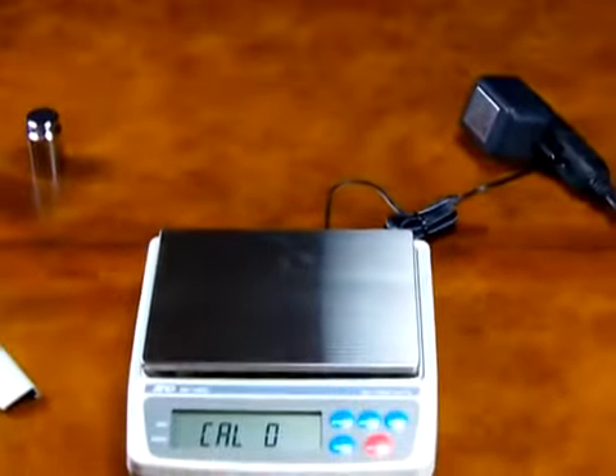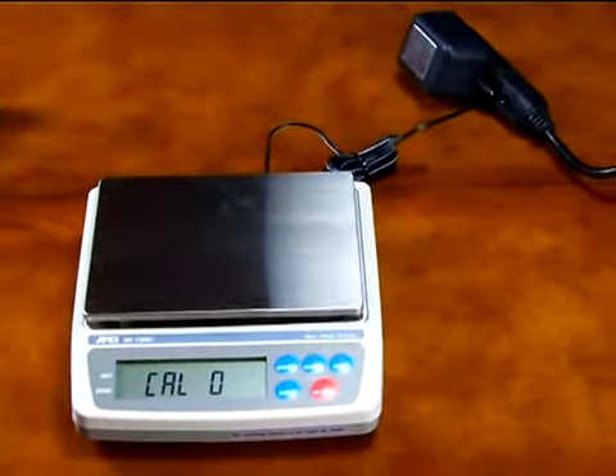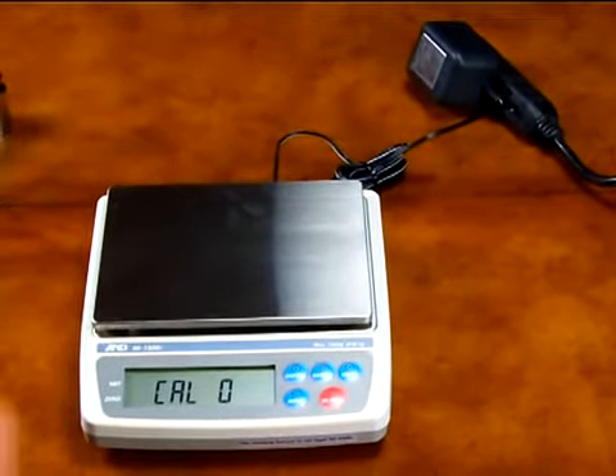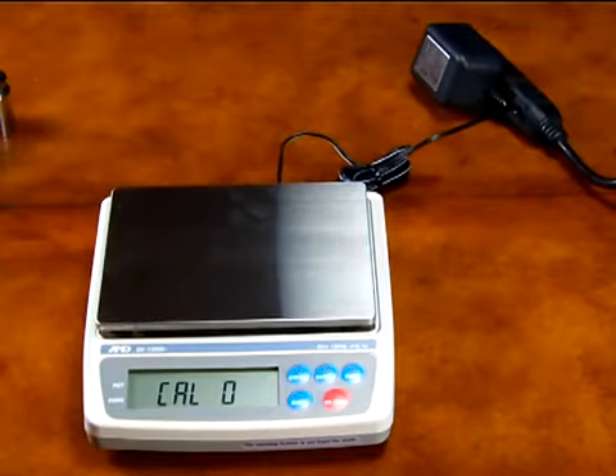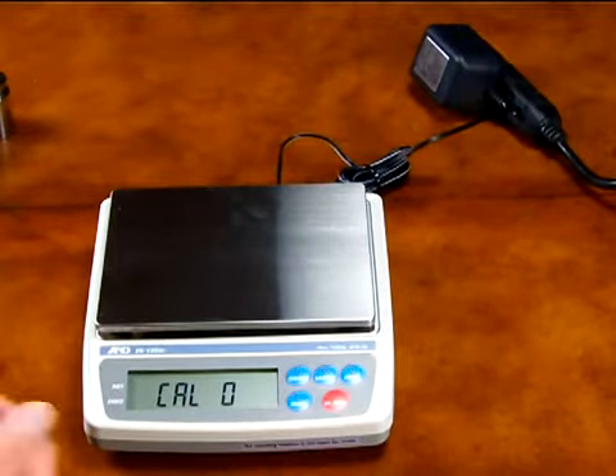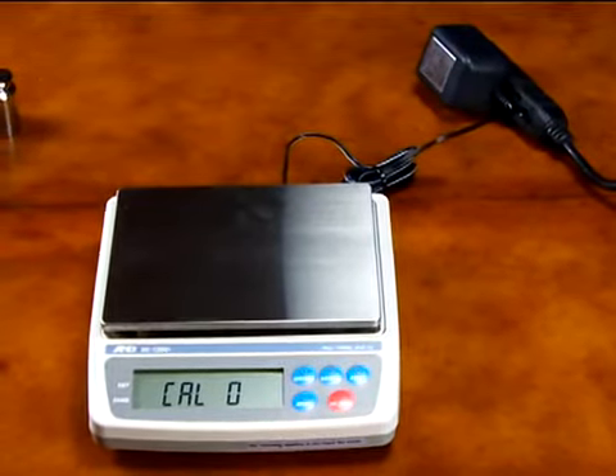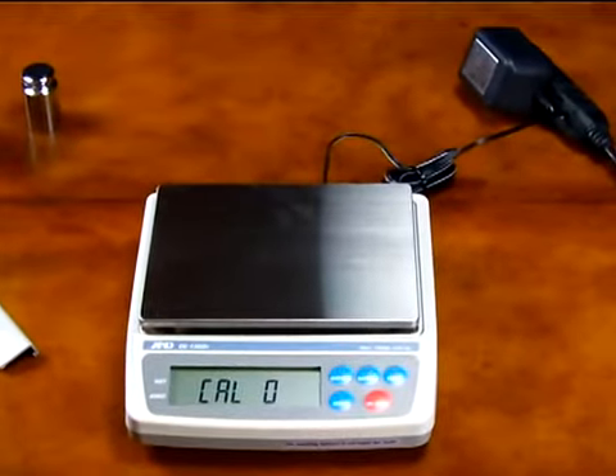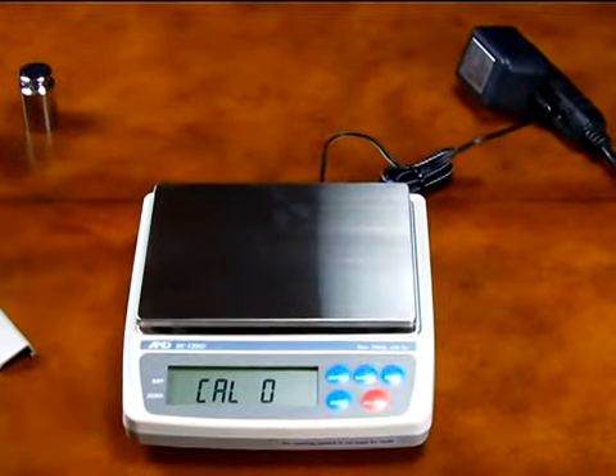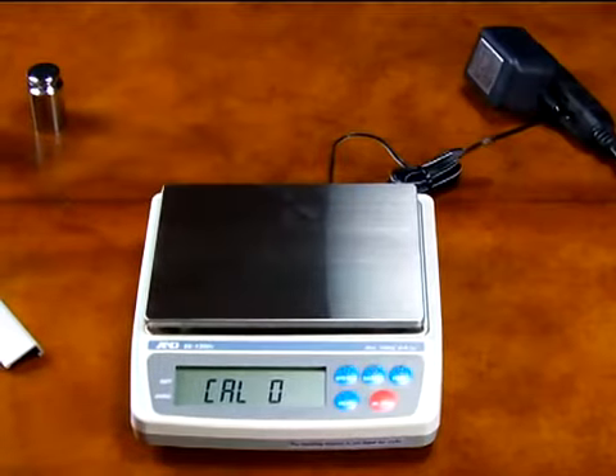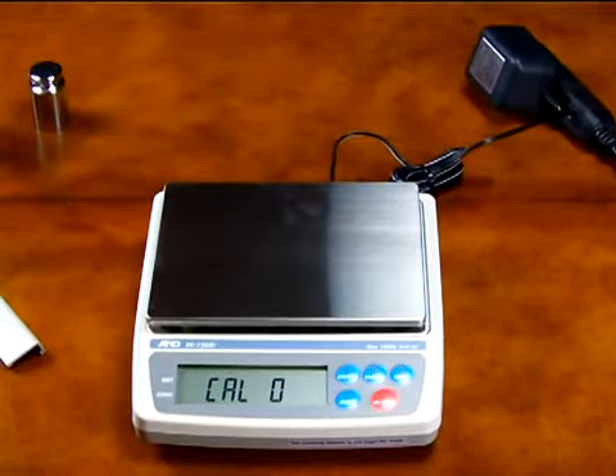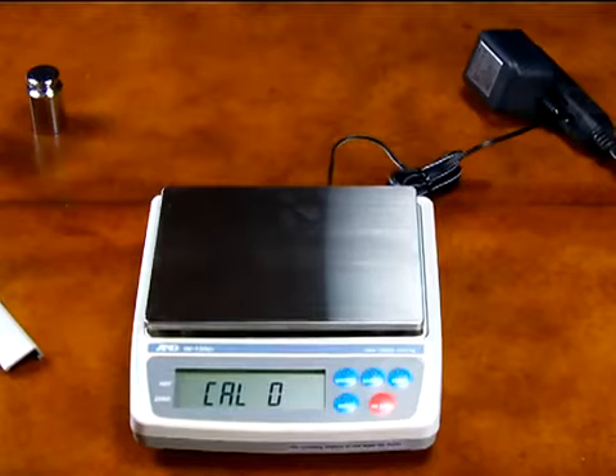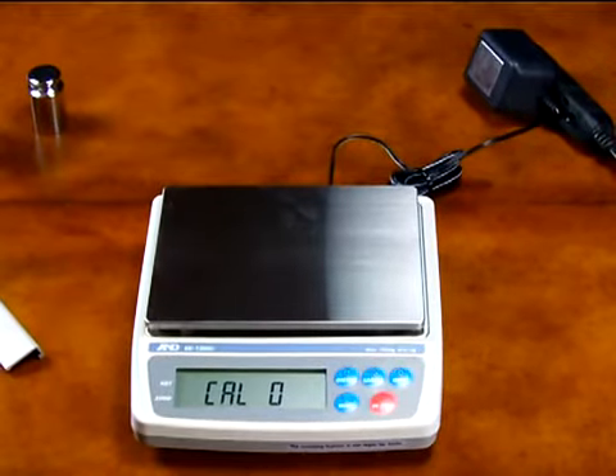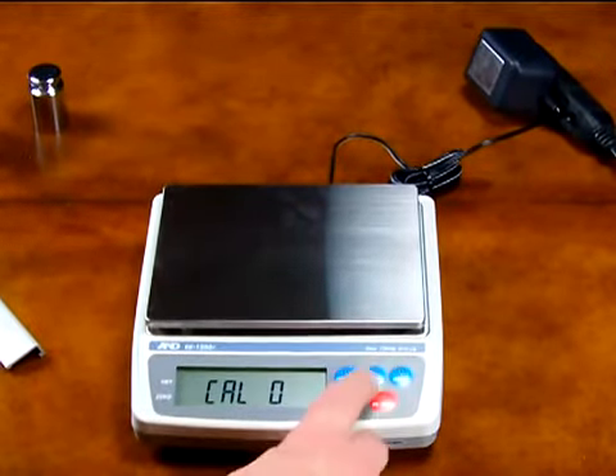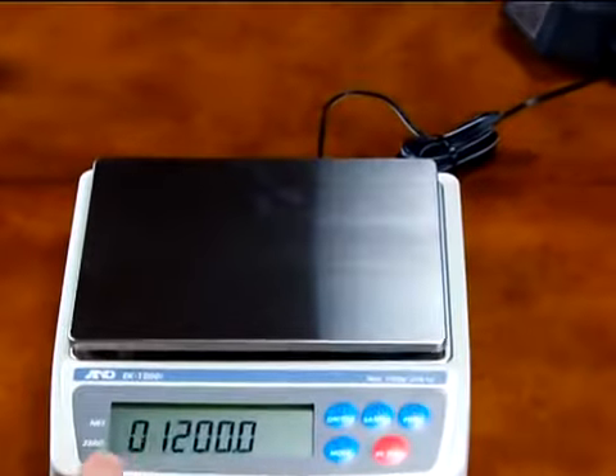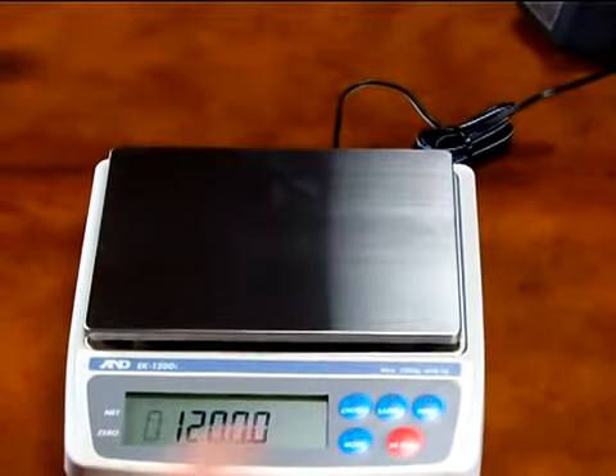So to start the calibration, the default with the A&D EK series, or the EK 1200i, is to be calibrated with a 1200 gram mass, but they don't sell a 1200 gram calibration weight. So you could buy a 1 kilogram and a 200 gram to equal 1200 grams, or we'll just change the weigh mode. To do this, we simply press the sample key, and you'll notice the default being 1200, and we need to change this.